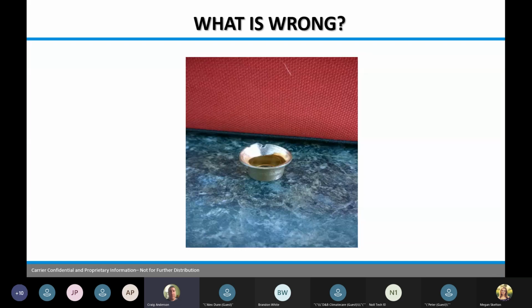So this is a flare. Like we were talking about the Loctite. If you flare it properly and you torque it properly, you're not going to have a leak. You're going to get brass on brass and it's going to seal. Getting a bigger wrench isn't solving the problem. You're going to mushroom it. You're going to make the problem worse. We do not need a lot of pressure to make these things seal.